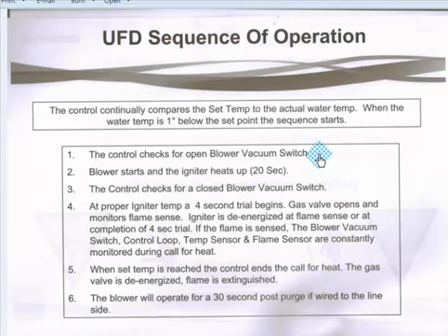We're smarter than you, I see it a lot of times - people just jumper out this vacuum switch. Well, guess what? The heater fooled you. It has to see an open vacuum switch. And people ask me, well, how long do I need to leave it not jumped and then jump it? And you don't know, it's up to the board. So if you got a bad vacuum switch, it's part of the safeties. Can't stress enough, you never, ever bypass a safety. Ever.